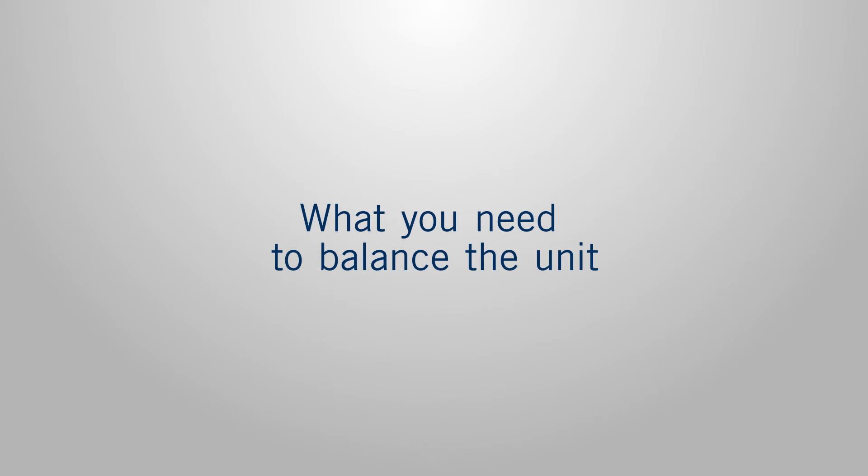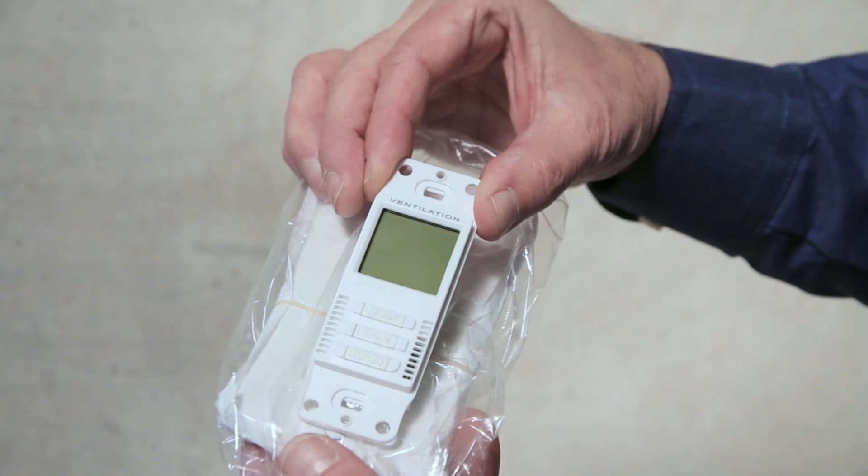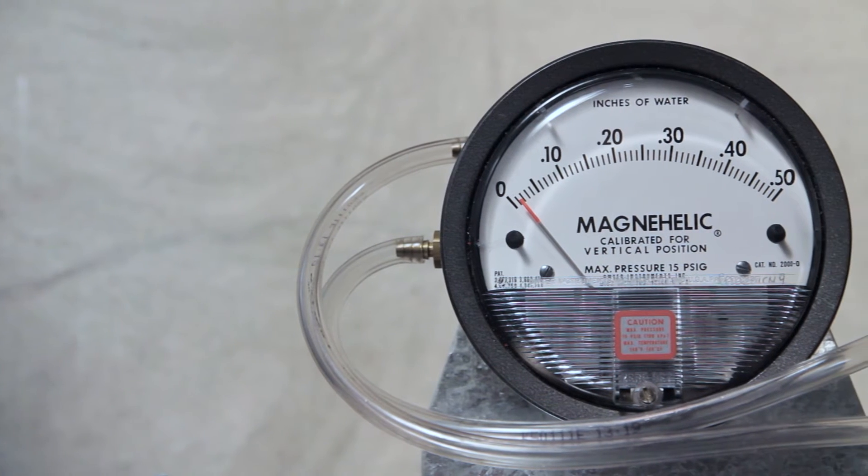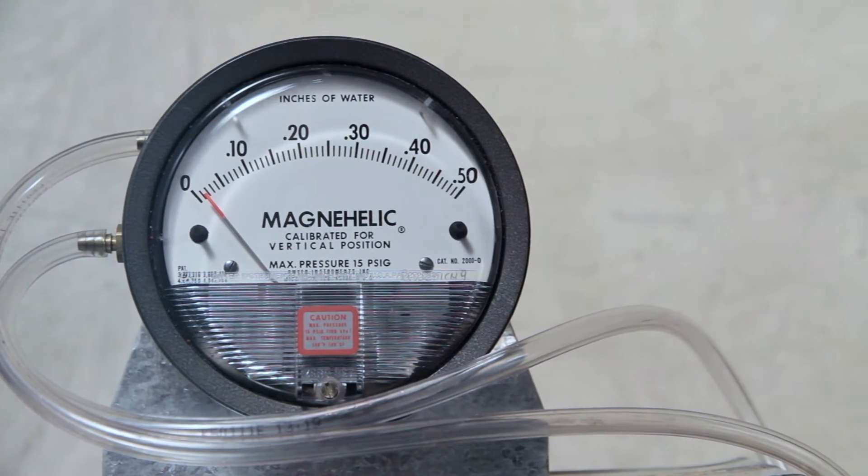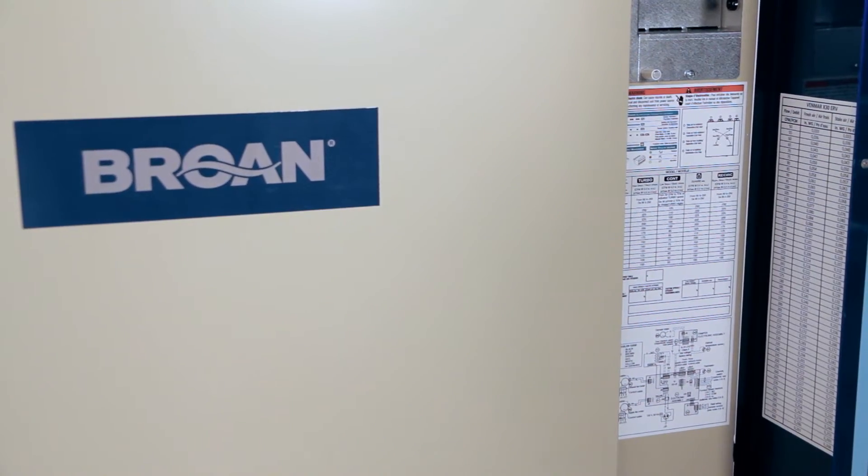It's important to note that you will require the following to perform the balancing: The HE Series Main Wall Control, a 0-0.5 inch water pressure gauge and two plastic tubes, and the balancing chart and preset table located on the unit.